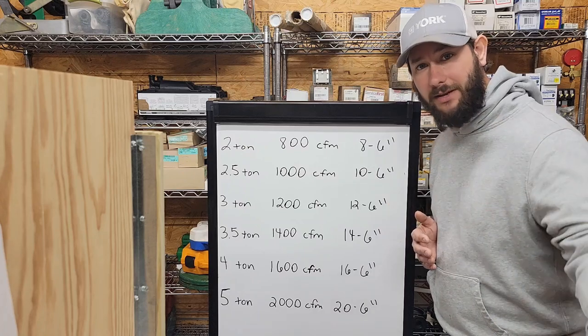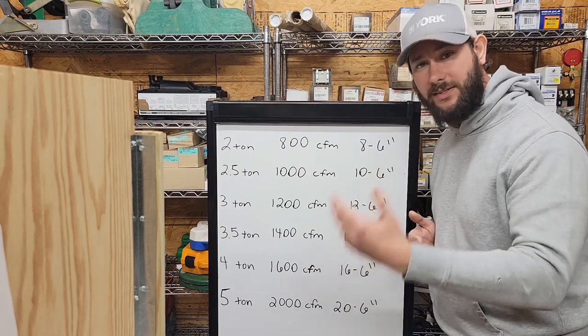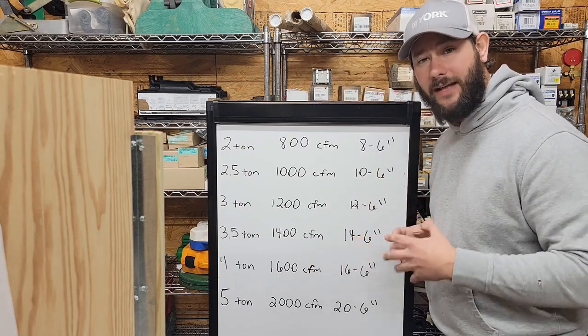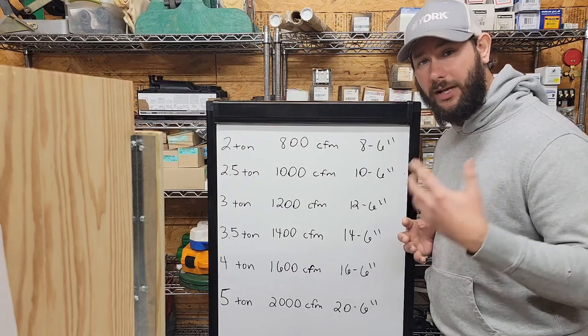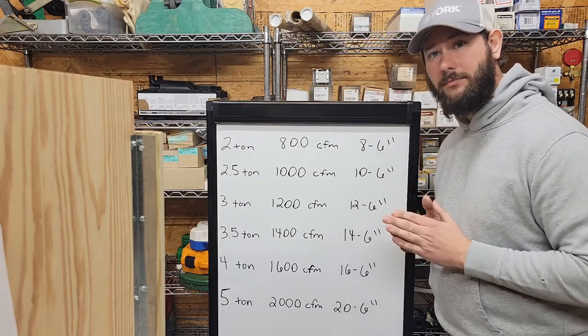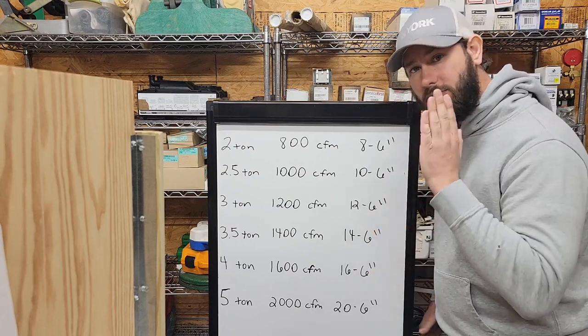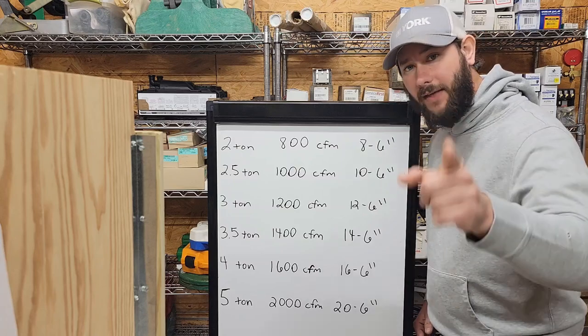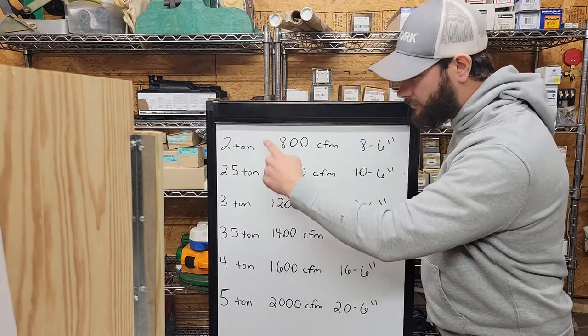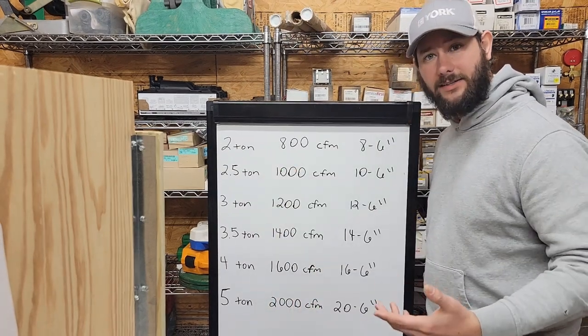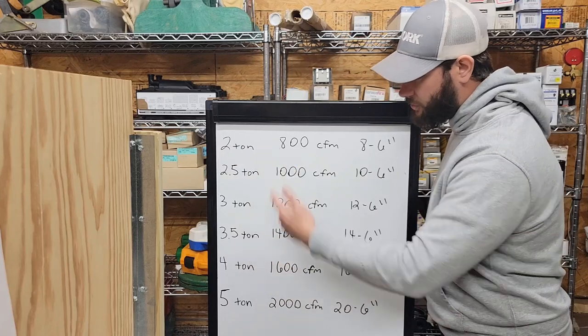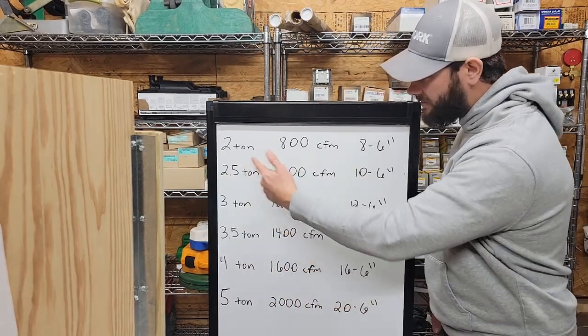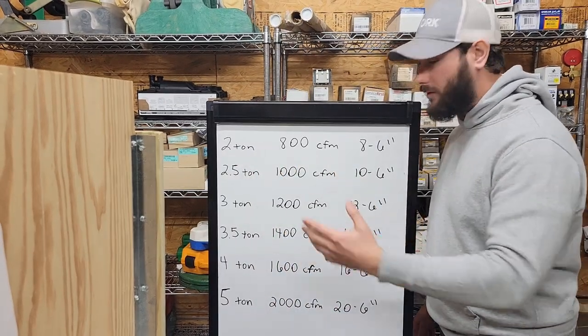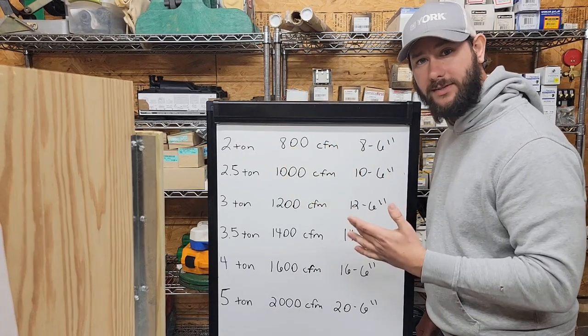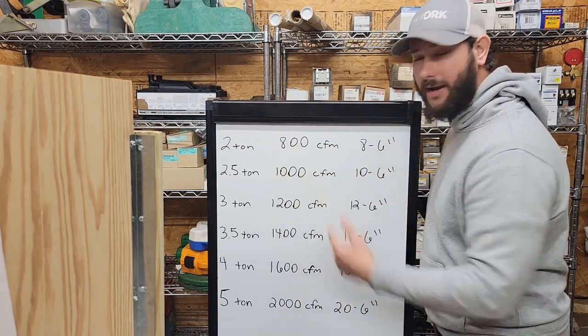You can use 350 to 450 CFM per ton, and that's going to make sure that you have good airflow. I'm using right in the middle of that, 350 and 450. I'm using 400 CFM per ton, and that's what you can use as well. This is in residential sizes for equipment here, from 2-ton to 5-ton. And beside each one, I have the total capacity, or the CFM, of that equipment.